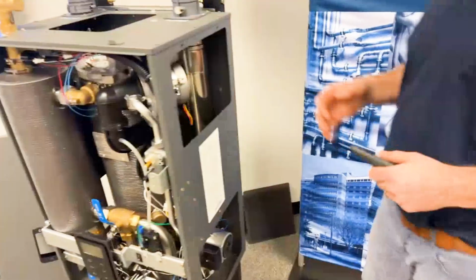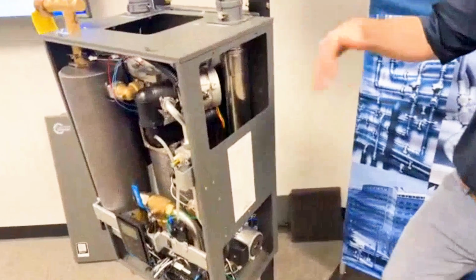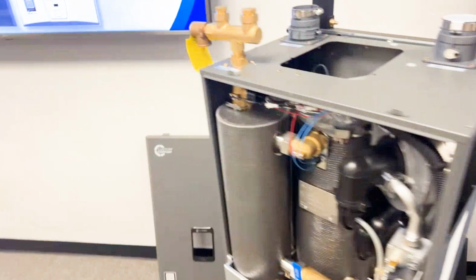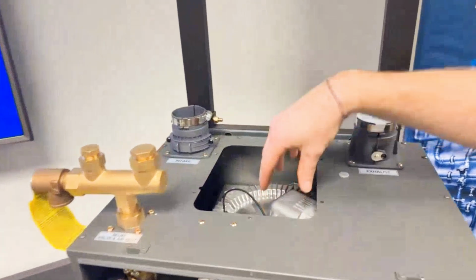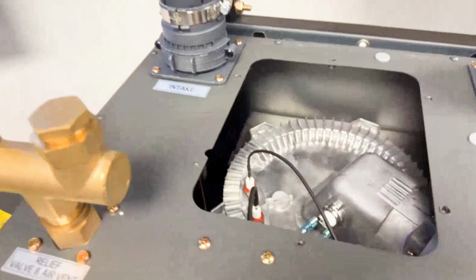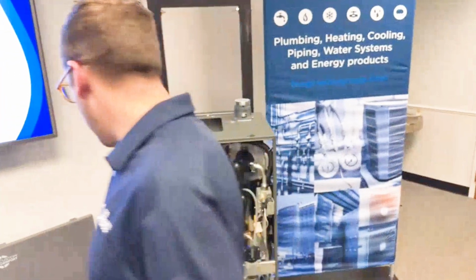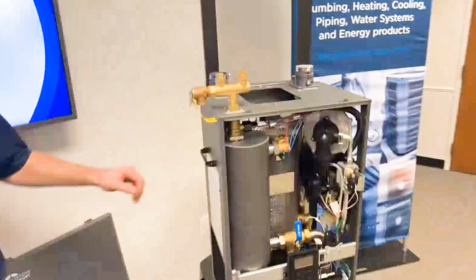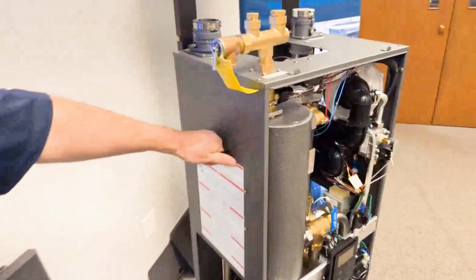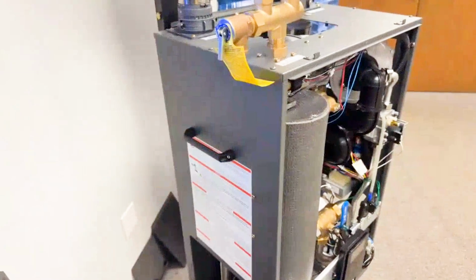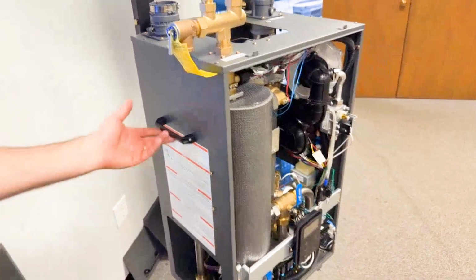So these access panels that I keep talking about, right? That's how we're getting to the parts and pieces of this boiler. And you've got 4 of them. You've got 2 on this side, 1 on the top, and 1 over here. And that's where you're going to access the inducer, the circulator, and the condensate trap. On top, you've got the access to the flame rod and igniter. So anything that you need to get to, you have access to. Super accessible, super easy to work on. Like I mentioned before, it's a heavy boiler. It's 150 pounds. We give you handles though, so you can mount this thing on the wall, right? Again, kind of the little things that make a difference when you're installing one of these. Try to think of all that stuff.